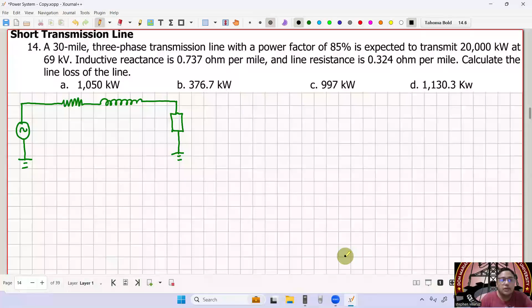So let's try answering some problems involving transmission lines. A 30 mile, three-phase transmission line with a power factor of 0.85 is expected to transmit 20,000 kilowatts at 69 kV. Take note: at the load, we will transmit 20,000 kilowatts, meaning that's at the load, so output power is 20,000 kilowatts, which is at the receiving end.